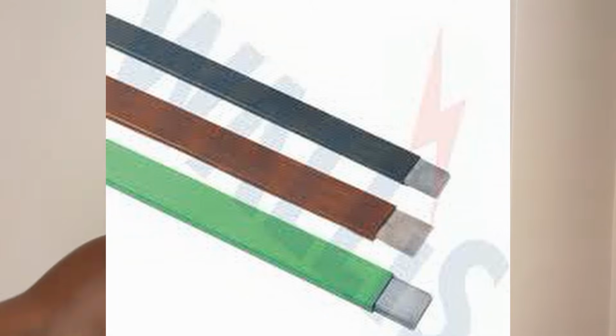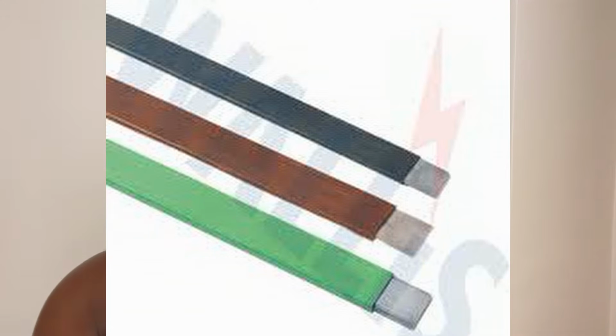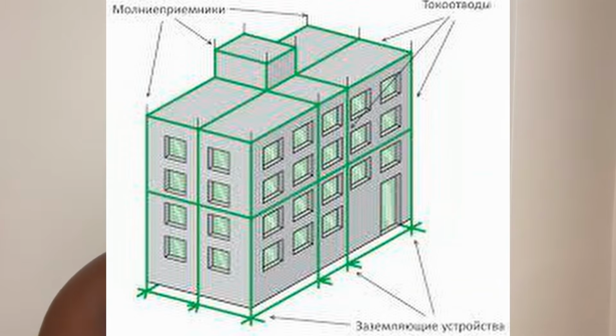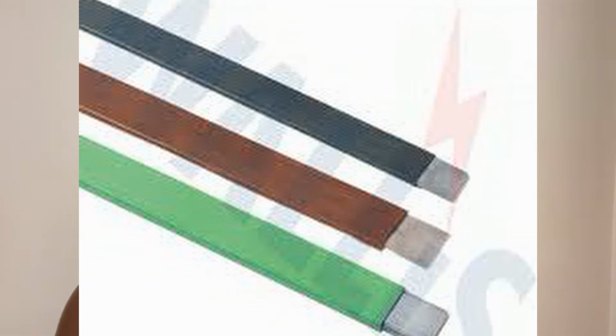Okay. Normally it is bolted on the surface of the building, but if you don't want to see it, when the block work is done, you can bring the tape onto the block work and plaster over the tape. And if you're going to plaster over the down conductor tape, you must use the one that has got insulation over the copper tape, because copper and concrete can have unwanted reactions. Okay. So that's the down conductor. It can be aluminium as well. Note, aluminium down conductors are a good product. It's not inferior. Aluminium down conductors are actually cheaper, okay?